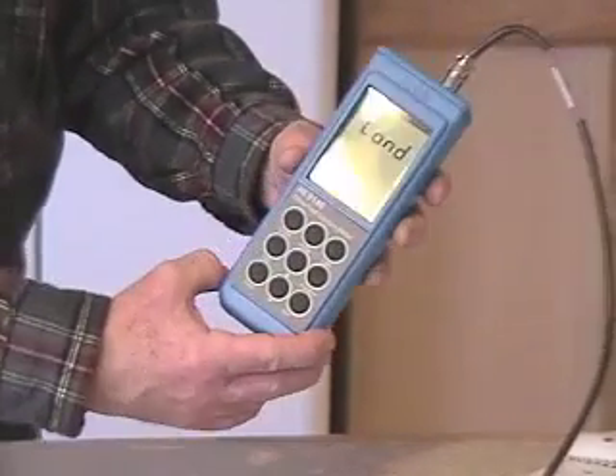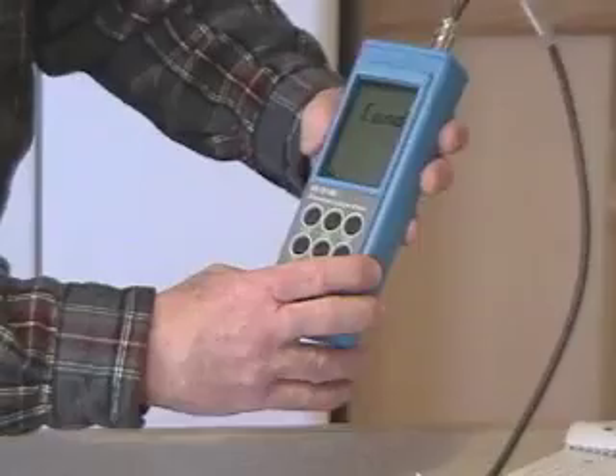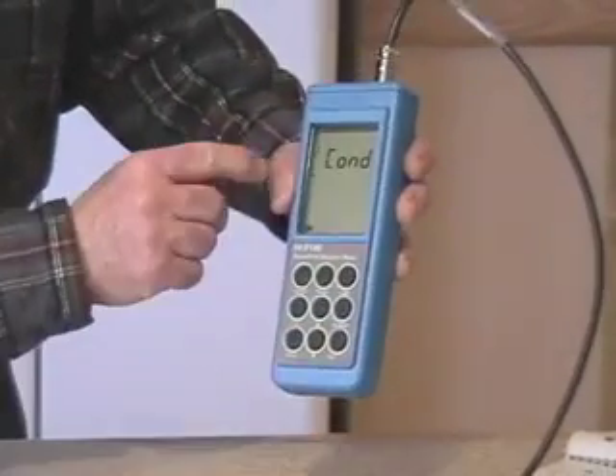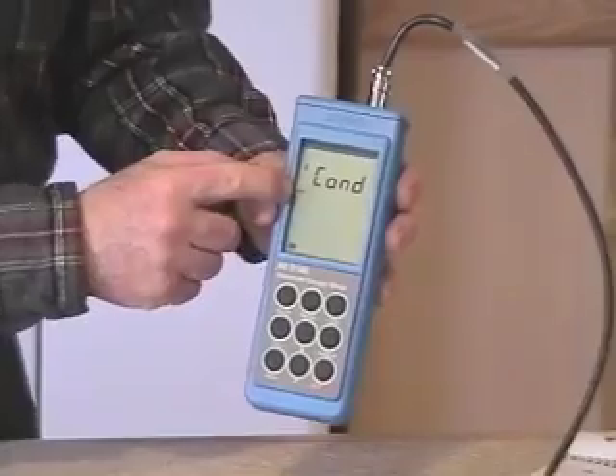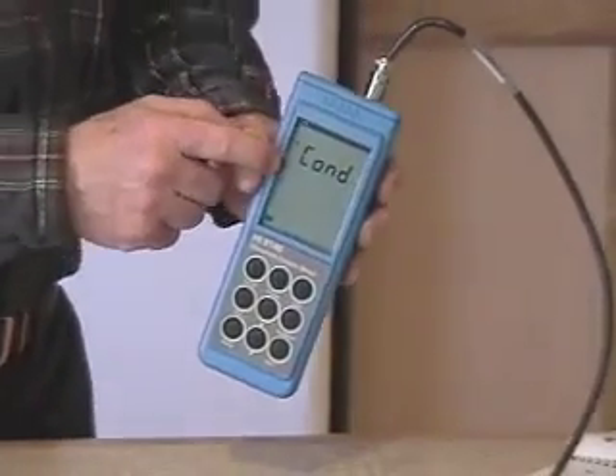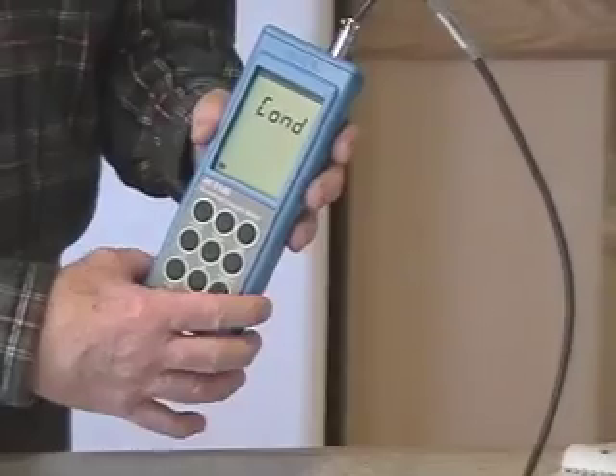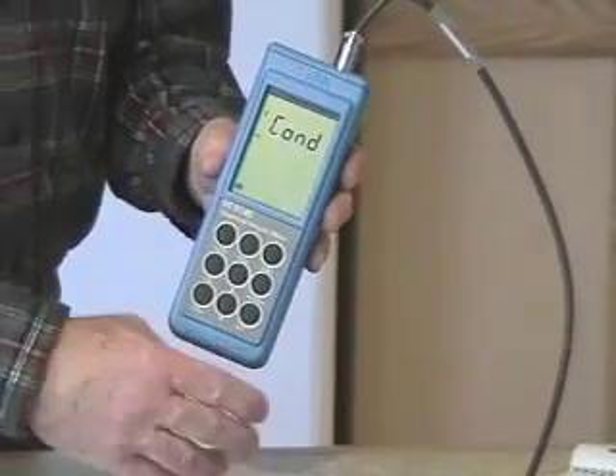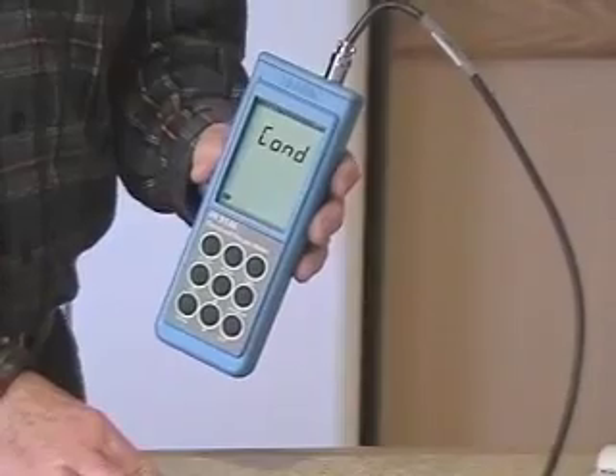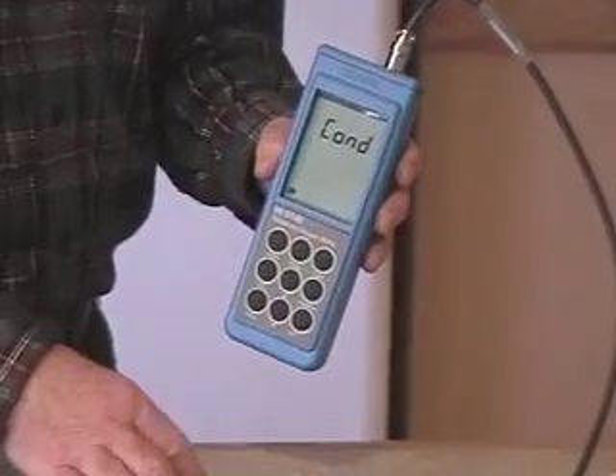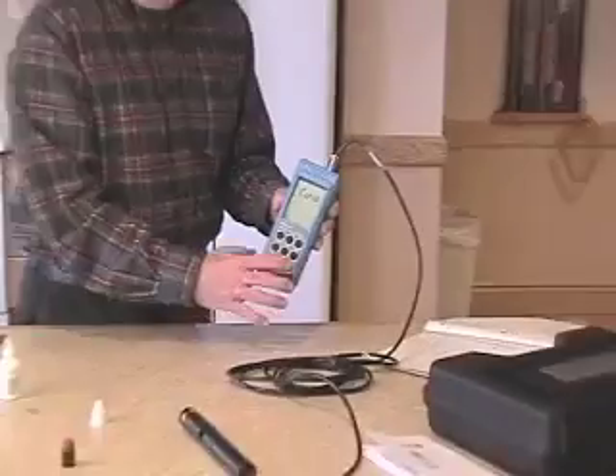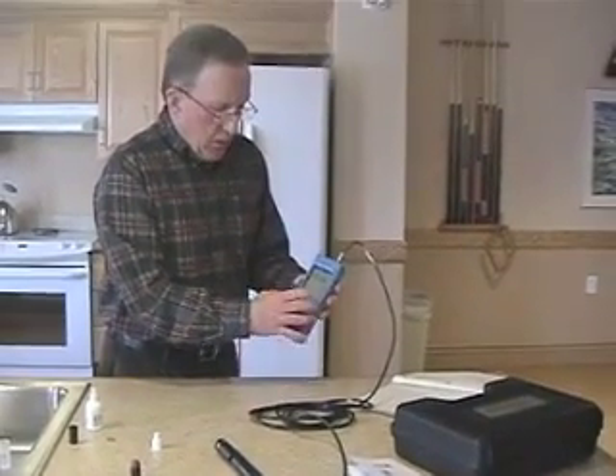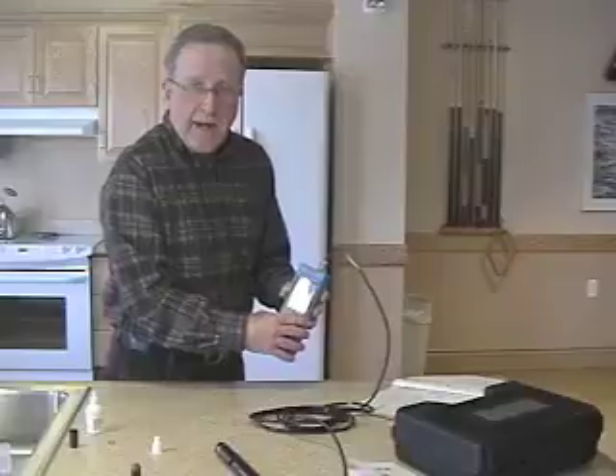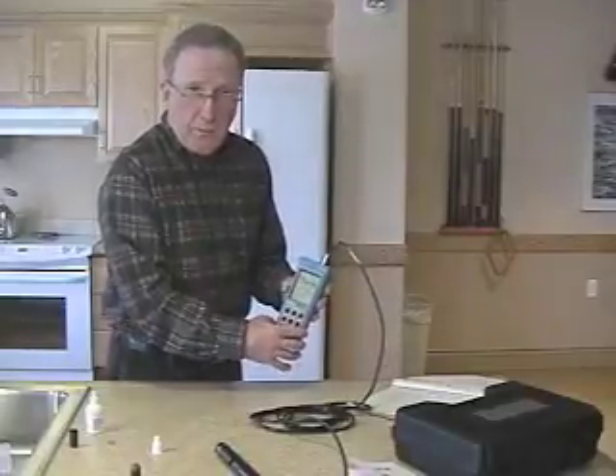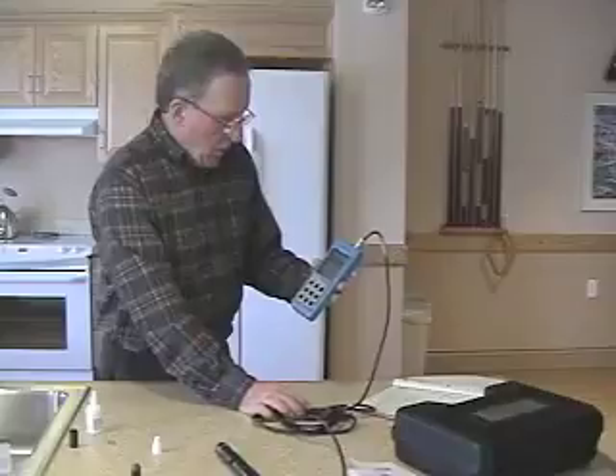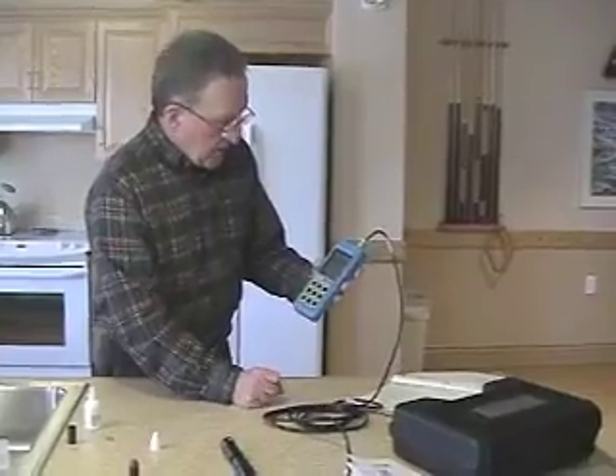Now it's in a conditioning mode, COND, and during the conditioning mode there's an X and a weight that are flashing. Those will flash until the meter is polarized. What it's doing is running an internal calibration, aligning all the circuits, making sure everything is functioning properly. It'll take a couple of minutes, but after it's polarized, then we can start calibrating the meter. While we're waiting, I'll show you the other 3 buttons that are on here.